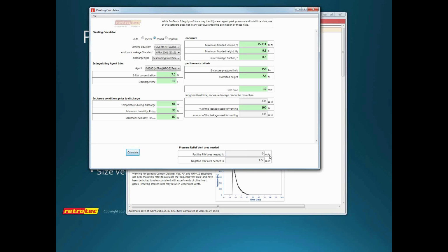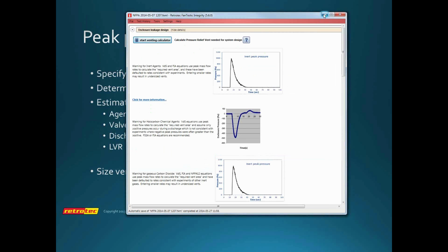And I can tell you that I've been there, I've seen the smoke going into the enclosure, I've measured the negative pressures personally. It's not something I've seen once or twice, I've seen it dozens and dozens of times, and it absolutely goes negative, no question. Okay, so we'll just set that aside for the time being.